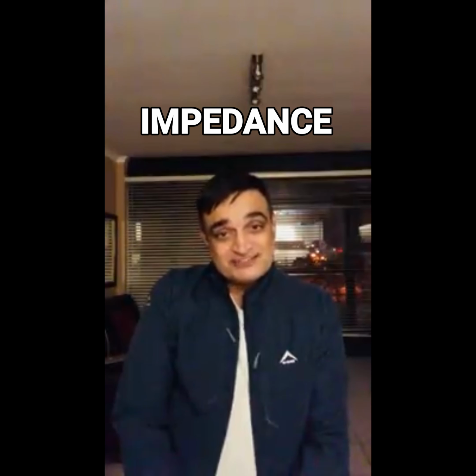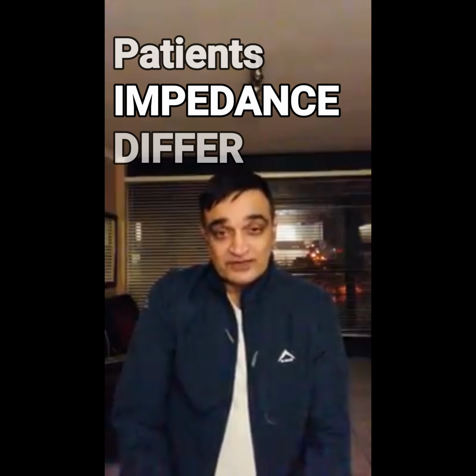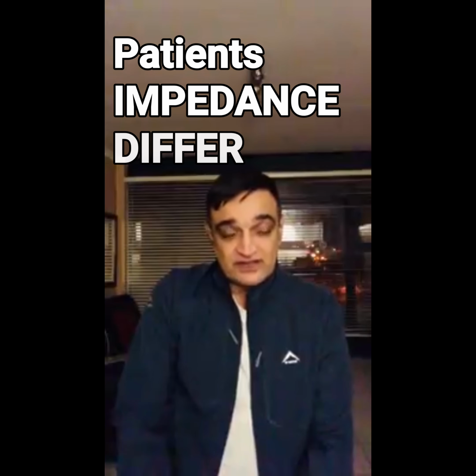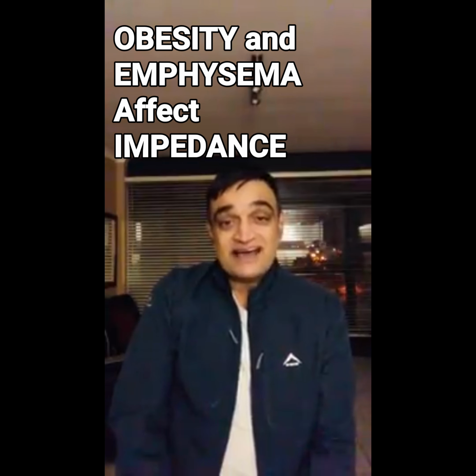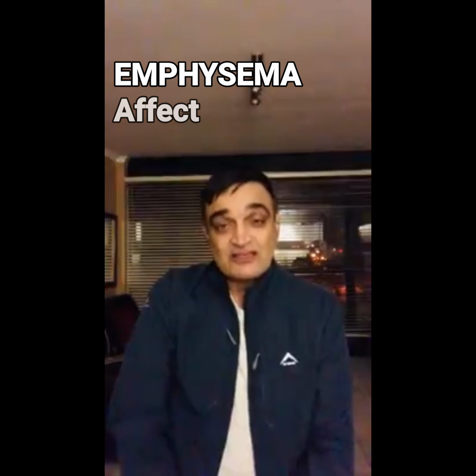The second thing is the impedance. The impedance is also known as resistance. And now the thing is, patients differ according to the amount of adipose tissue and air in the lungs. Some people have emphysema, and that affects impedance. The impedance is higher in patients that are obese. So what's needed is multiple shocks to overcome the impedance.